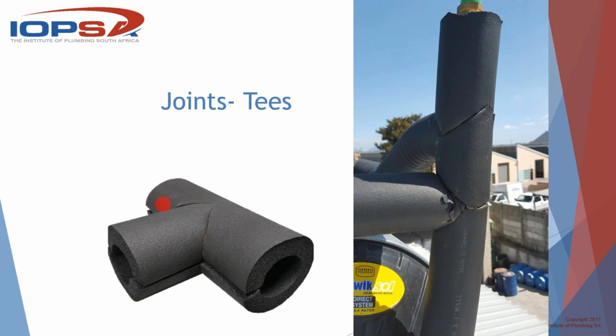You've got a perfectly shaped T, and then you cut the thing open like that, and you'd make 10 of those in your workshop, bring them to site and pop them over all the T's. These on the right-hand side weren't done like that. It was done on site, in situ, with a lot more effort, I want to tell you. This is a lot more difficult than pre-making your tees, because these glued joints have no detrimental effect on the lagging itself if they're nicely glued with proper cement. So this is an excellent idea: you spend an hour or two in the workshop, make three or four or five of these things, and man, it's simple. You halve your time on site trying to cut and lag and miter and join. So that's a nice little hint that I came across recently as well.